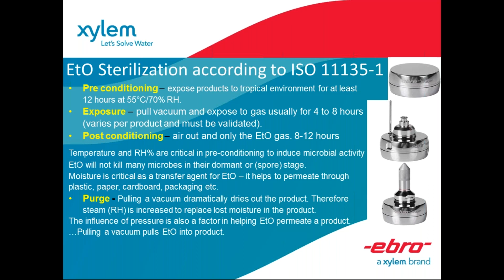Then the last cycle or phase is the purging, which is pulling a vacuum dramatically to dry the product. So therefore steam is increased to replace lost moisture in the product, and this influence of pressure is also a factor in helping ethylene oxide permeate the product. So pulling a vacuum pulls ethylene oxide into the product, as simple as that.